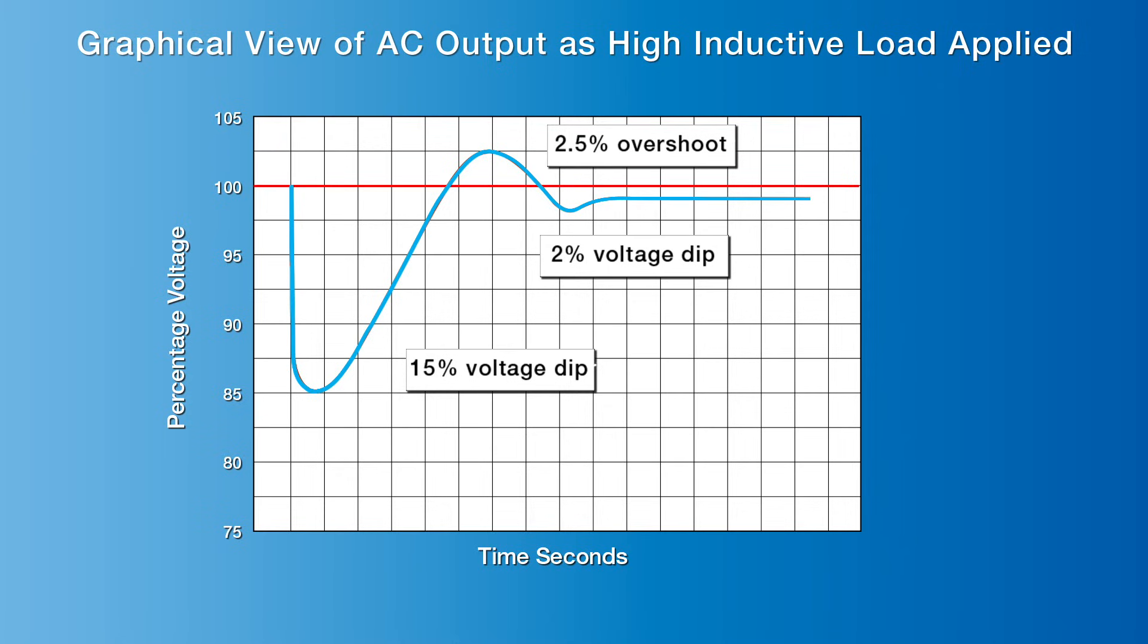During the starting phase, the self-excited generator's reference voltage to the AVR drops, and the AVR will feed more DC volts to the exciter coils to increase the main rotor's magnetic field to increase stator output voltage.